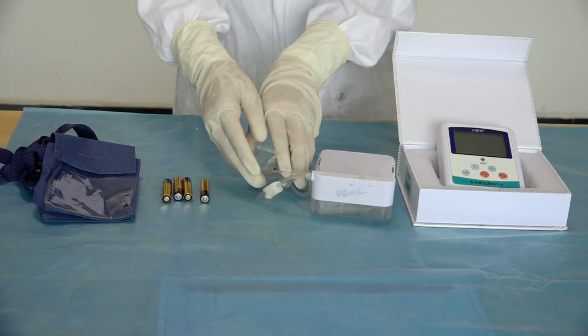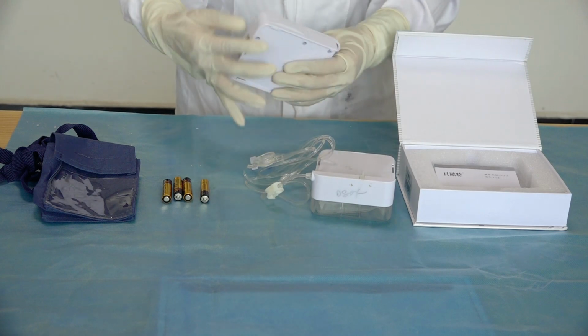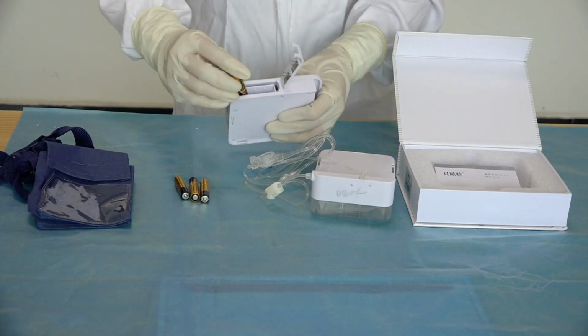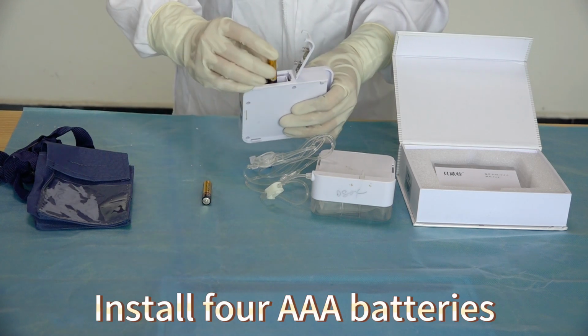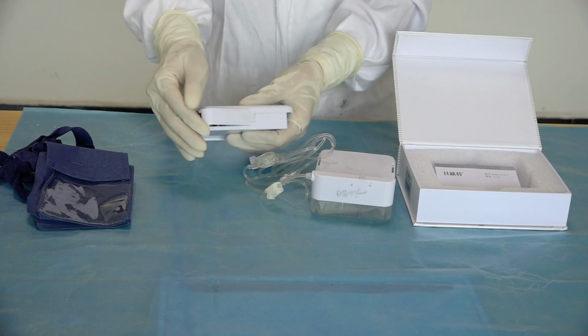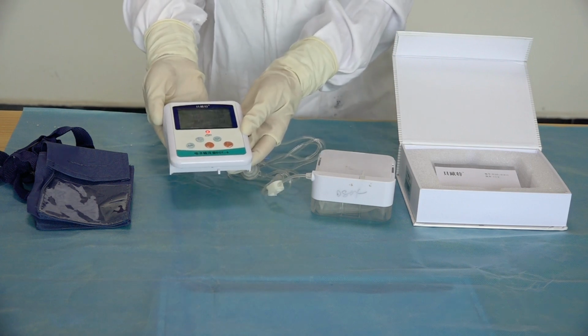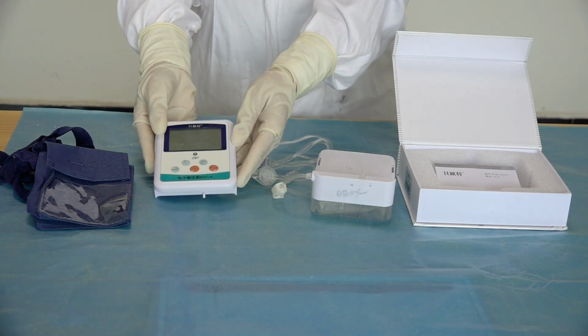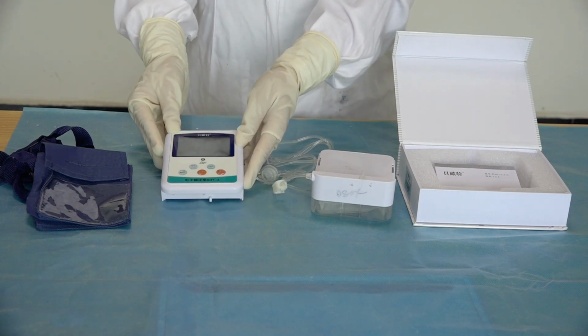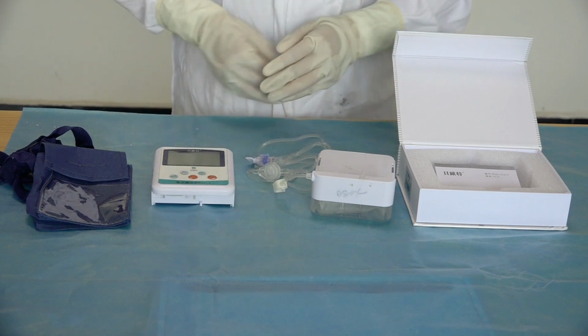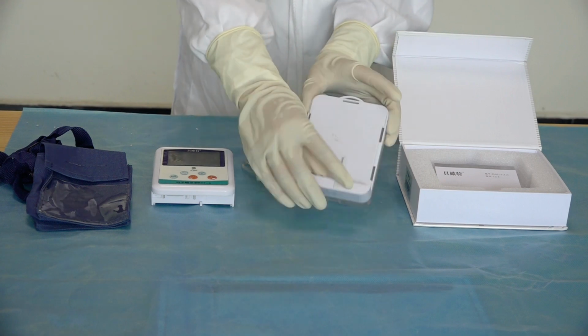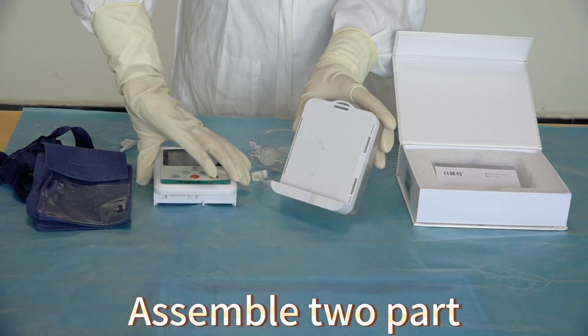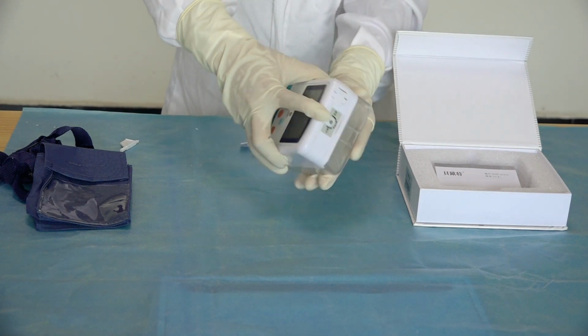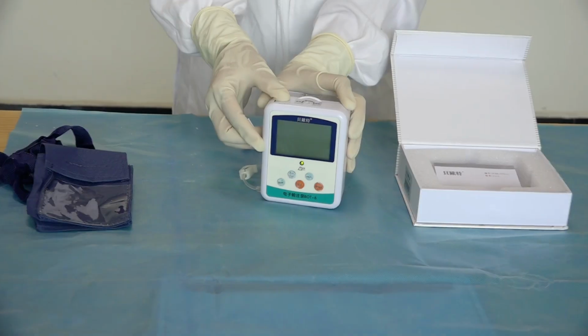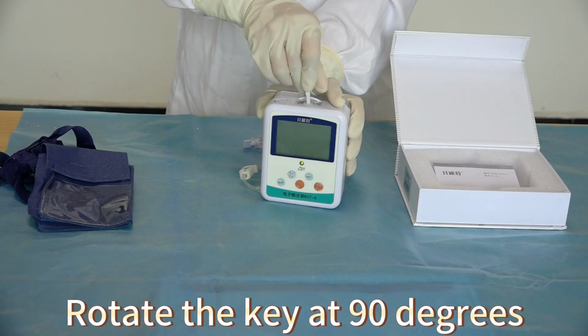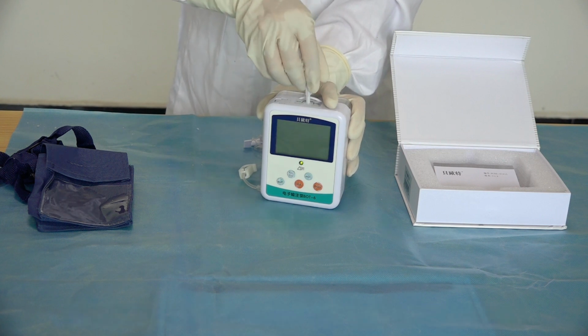Step 2. Take out the electronic components, open the battery cover. Install 4 AAA batteries according to the positive and negative poles of the battery and close the battery cover. The green light indicates that the pump is normal and ready for use. Step 3. Remove the key, assemble the liquid storage component to the electronic control component. And rotate the key at 90 degrees in the locking direction to lock it.